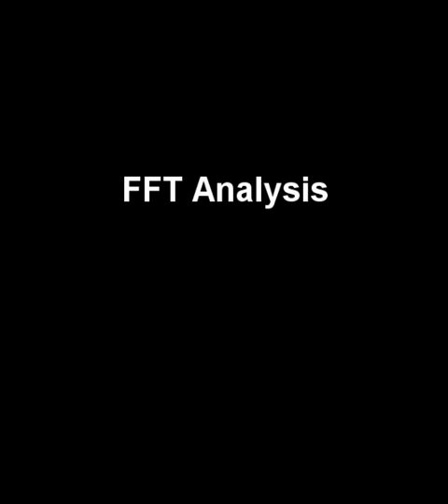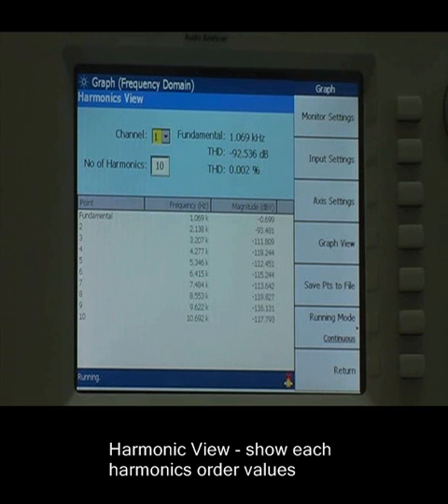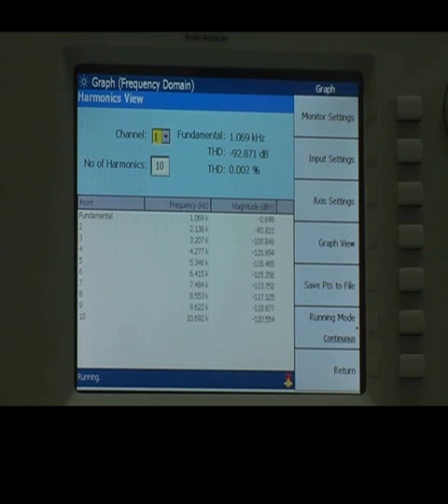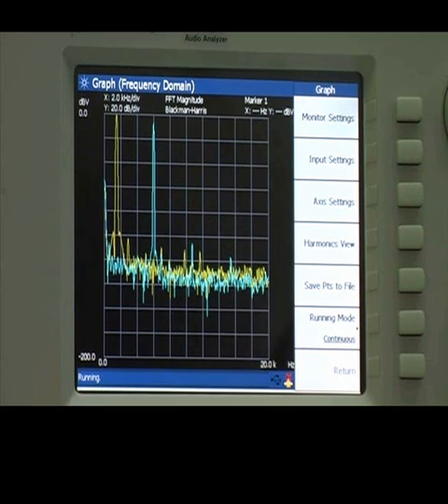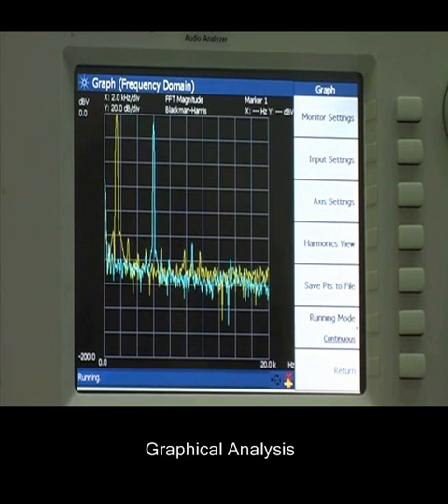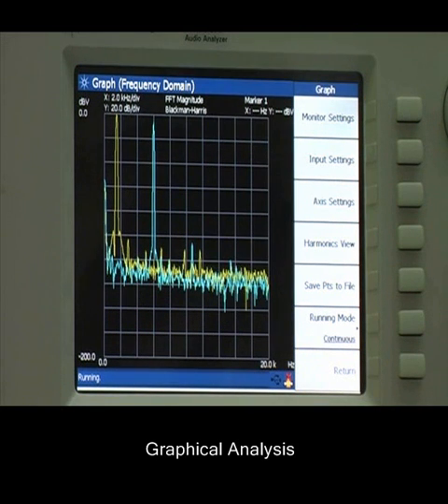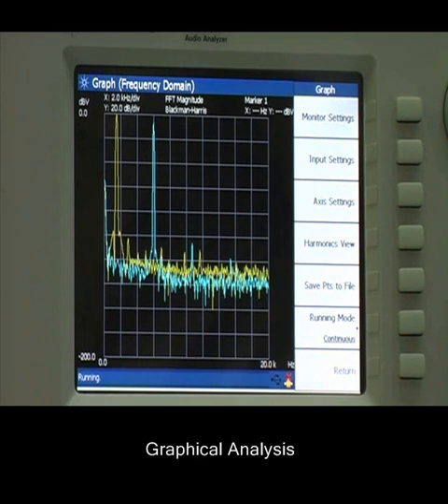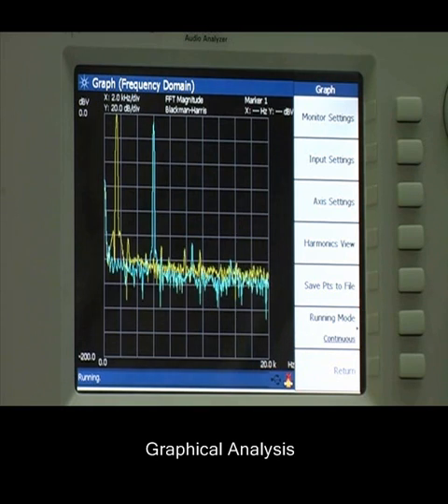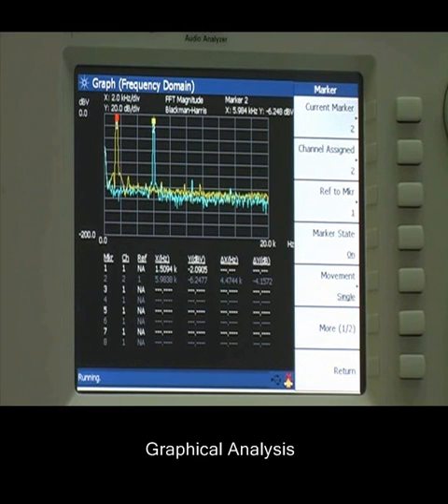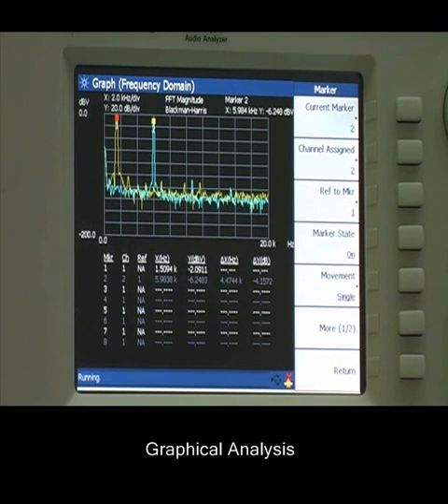The U8903A also provides FFT analysis capabilities. With harmonics view, you can see each harmonic order value. The raw data can also be saved into an Excel file. With graphical analysis, you can make peak signal measurements and signal-to-signal measurements. The graph can be saved as a JPEG file format.